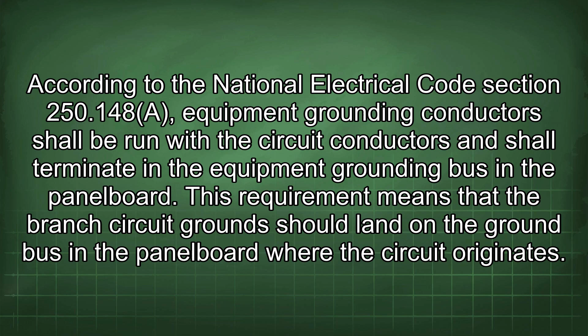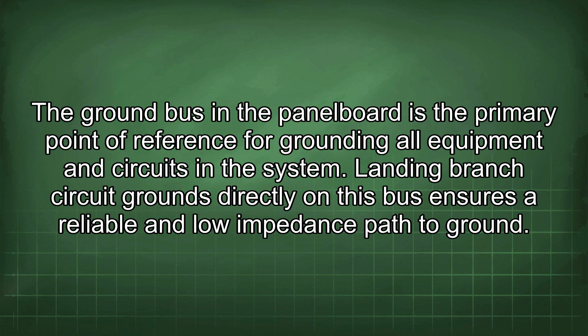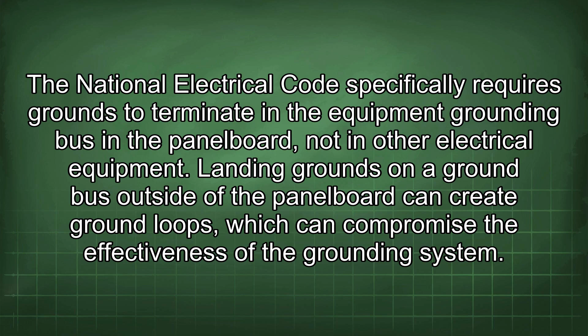The ground bus in the panel board is the primary point of reference for grounding all equipment and circuits in the system. Landing branch circuit grounds directly on this bus ensures a reliable and low impedance path to ground. The National Electrical Code specifically requires grounds to terminate in the equipment grounding bus in the panel board, not in other electrical equipment. Landing grounds on a ground bus outside of the panel board can create ground loops which can compromise the effectiveness of the grounding system.